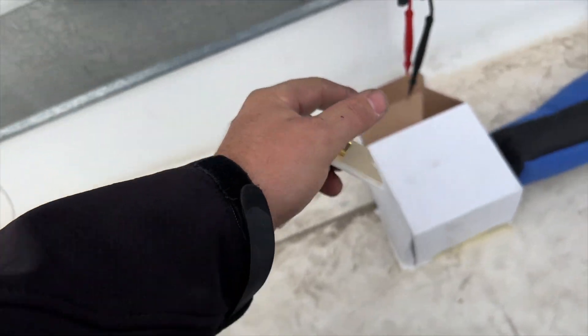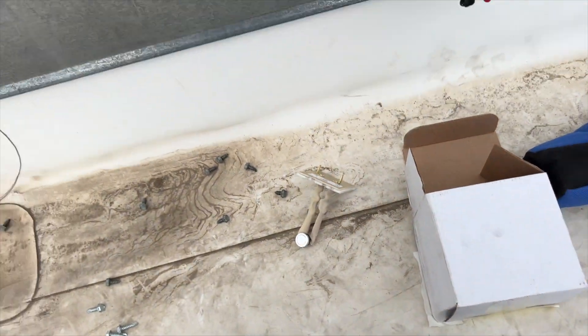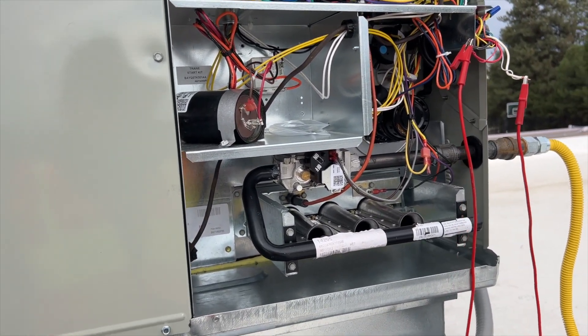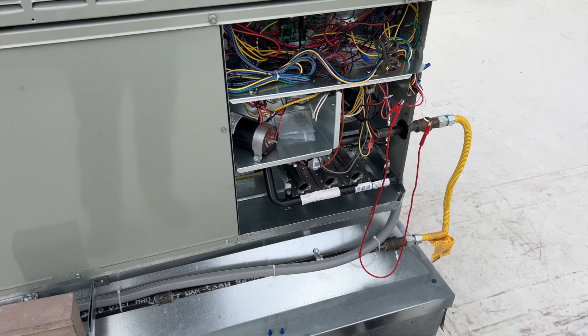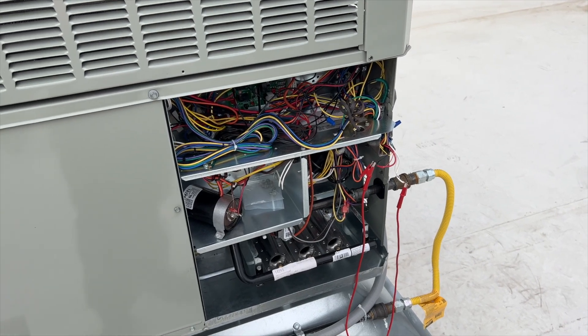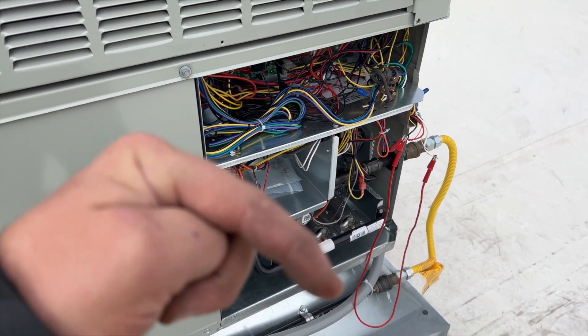Here's the new one — I'm going to open it up and make sure it works before I swap it out. It is closed, good. We got the new one in there and we're calling for heat to make sure. This is the old one, we'll turn that in for warranty. She's been running for about 15 minutes, everything seems fine so we're going to call it. Even a brand new system can have defective parts apparently — just because it's brand new doesn't mean you won't have a failed part. Hopefully this helps you out, thanks for watching.